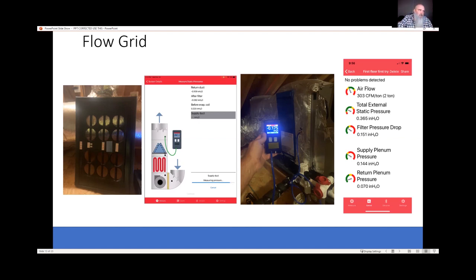Or let's be specific about it. It's a scapegoat for contractors that are kind of shady. In any instances that I've been involved with as a utility representative, high bill complaints, finding heat pumps where something was wrong, I would go back to the contractor and say, here's the deal. There's something wrong with this piece of equipment. I suspect it's overcharged. And you can do all this through a process that's non-invasive.